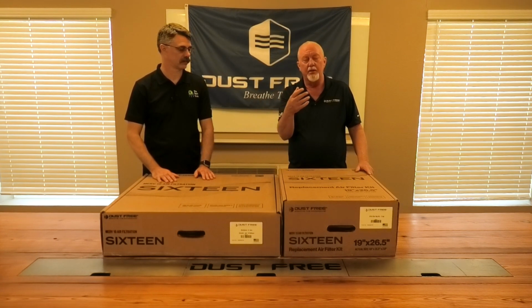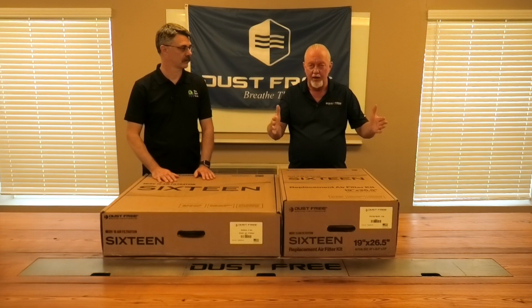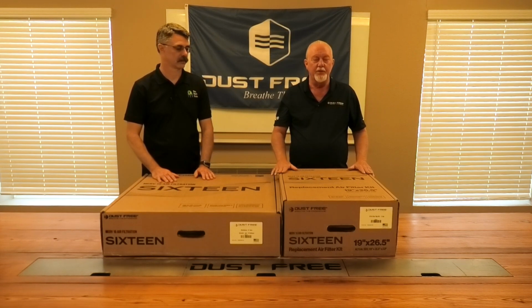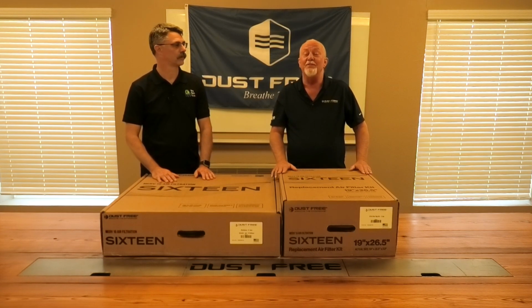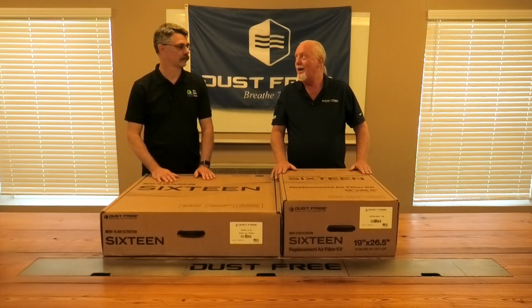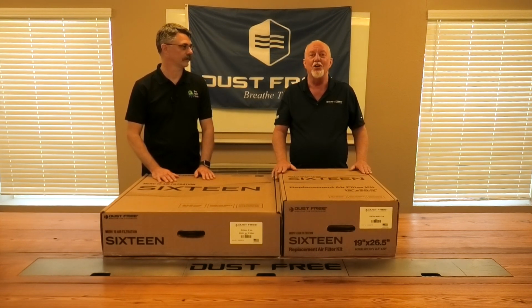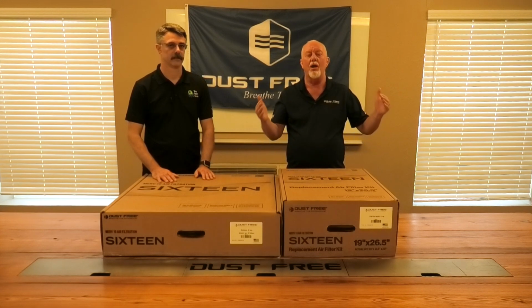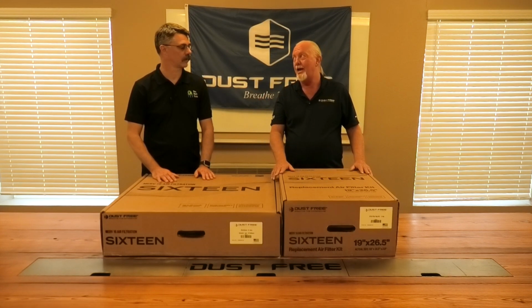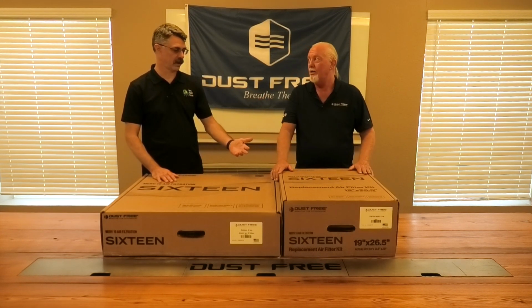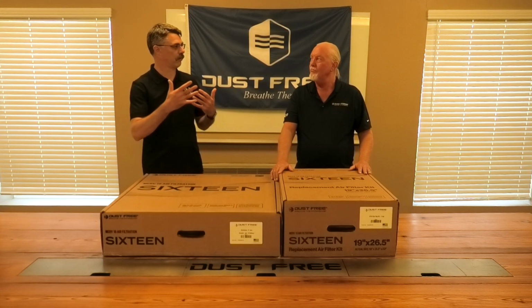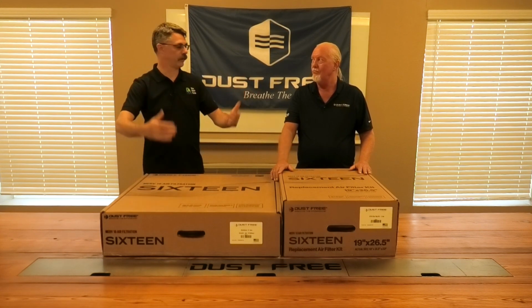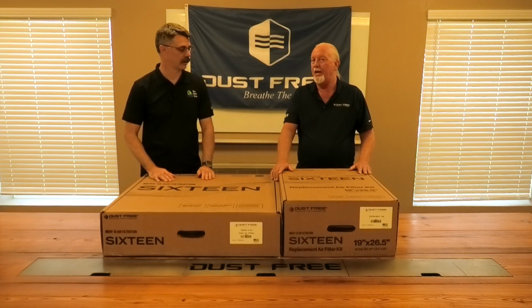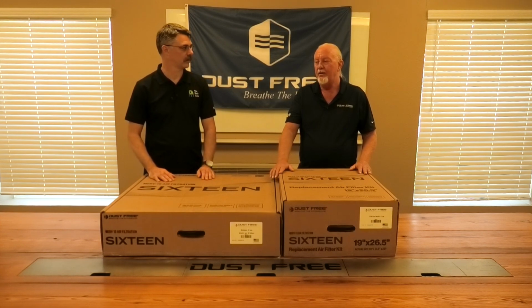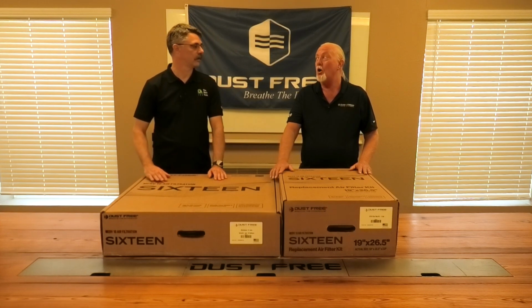So I mentioned that the bulk of the industry has a panel filter. Well, this filtration setup uses V-bank. So what that allows us to do is have an astronomical amount of surface area. It's all about the surface area, and that's why we're able to achieve very low static drop. More surface area means less static drop, because you've got a larger area to move that volume of air through. Yep. And with that surface area, we get longer lifespan.